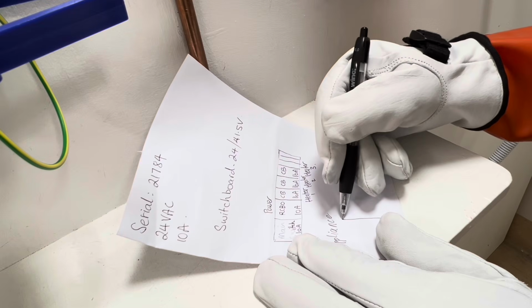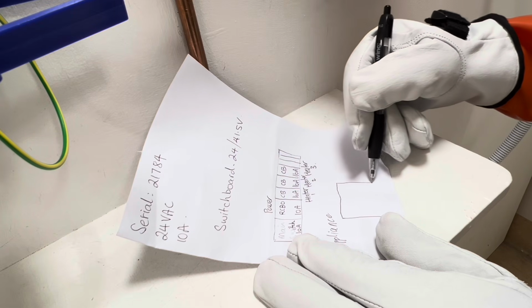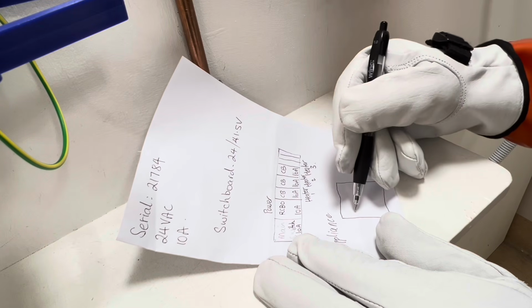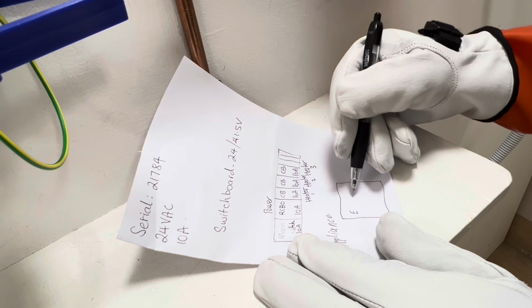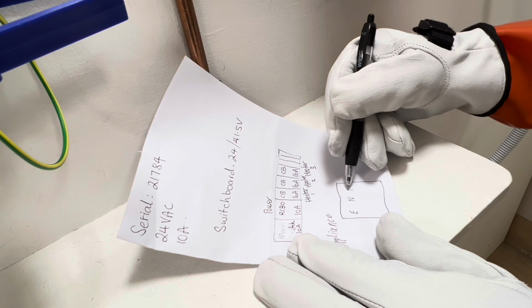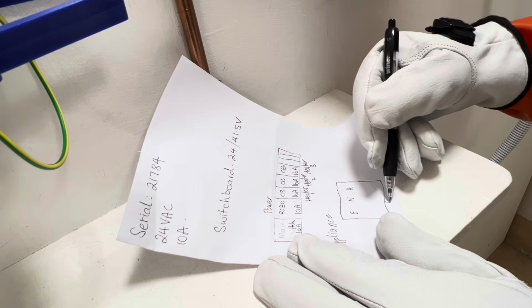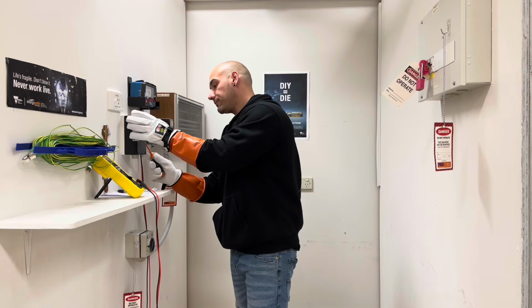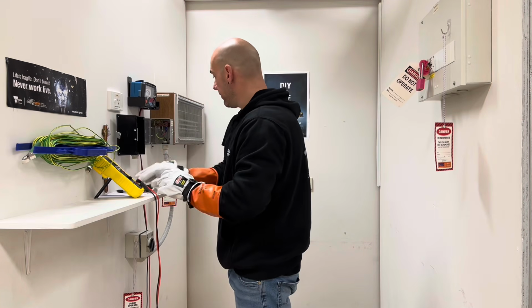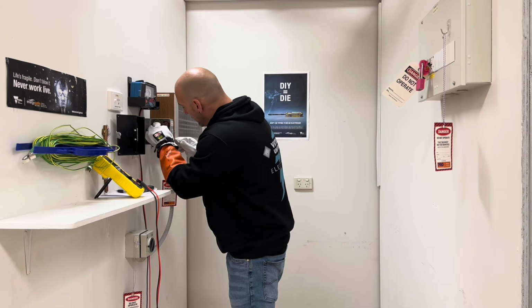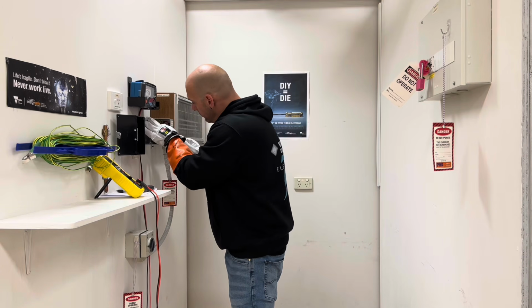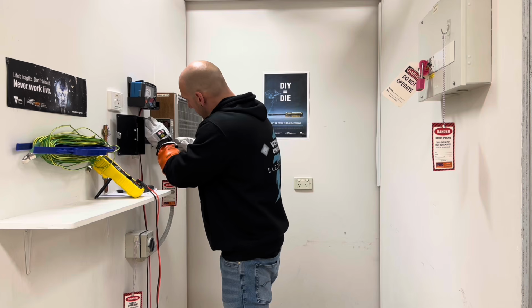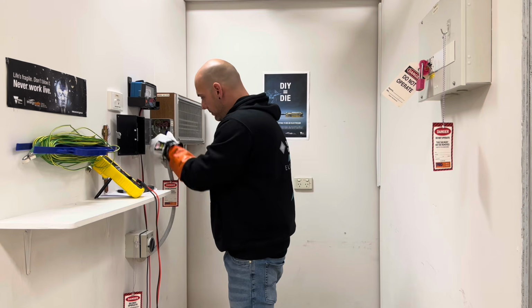Before I disconnect anything, I'm going to get a diagram of the terminal block. Terminal block, conduit to the bottom, and we have an earth, neutral, active. I'm going to remove the active first, neutral, and earth, conduit.